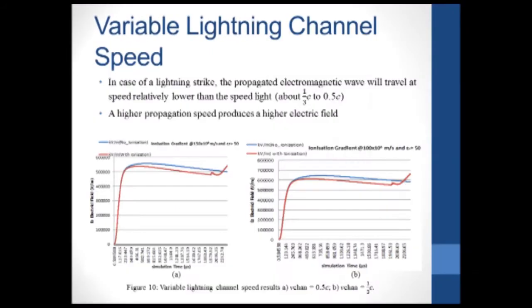In case of lightning strike, the propagated electromagnetic wave will travel at speed relatively lower than the speed of light. We've computed simulations using 33% and 50% speed of light. Our result shows that the higher propagation speed produces a higher electric field.